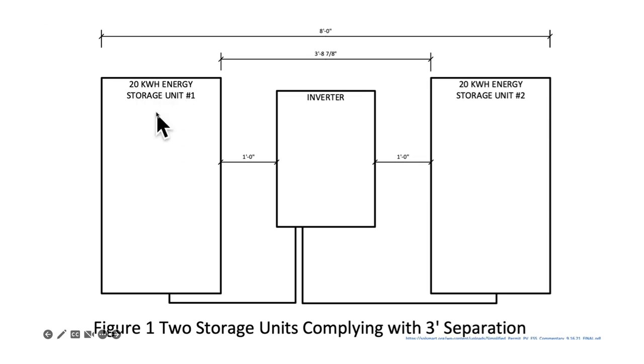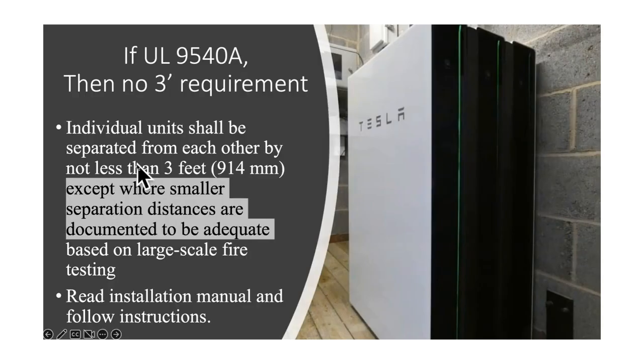And so here we're showing 2 different 20 kilowatt hour energy storage systems separated by an inverter. And once again, large scale fire testing could let it be. So like the Tesla Powerwall, you could stack 2 of these right on top of each other according to instructions. So individual units shall be separated by 3 feet, except where smaller distances are documented to be adequate based on 9540A, which is large scale fire testing. I read that in the instructions. So that's just typical for the Powerwall.